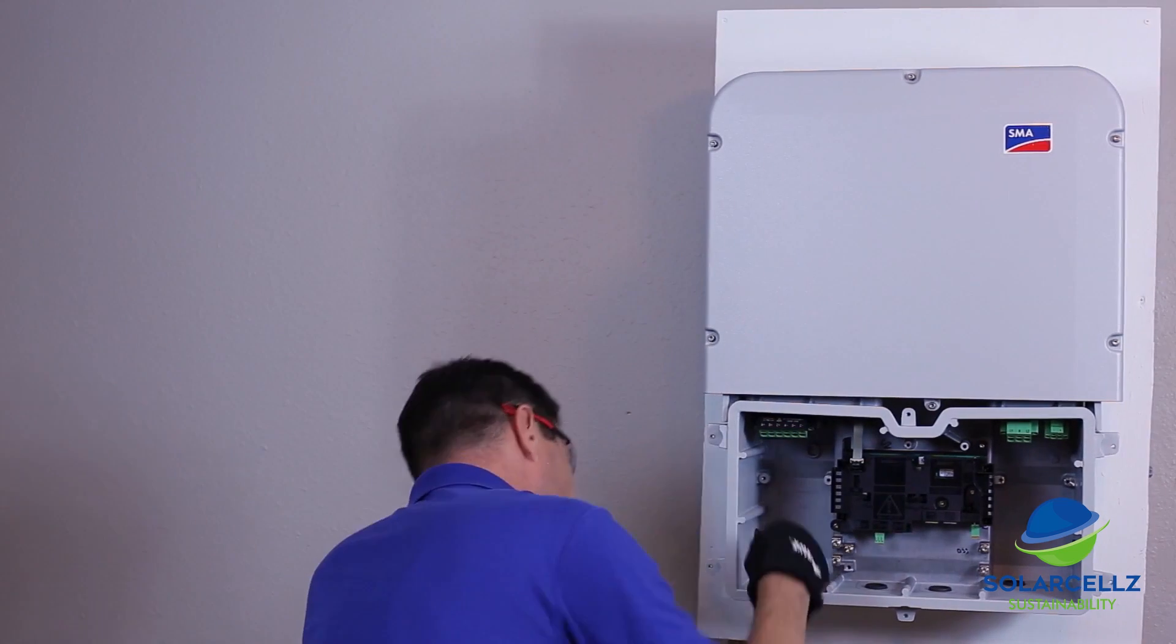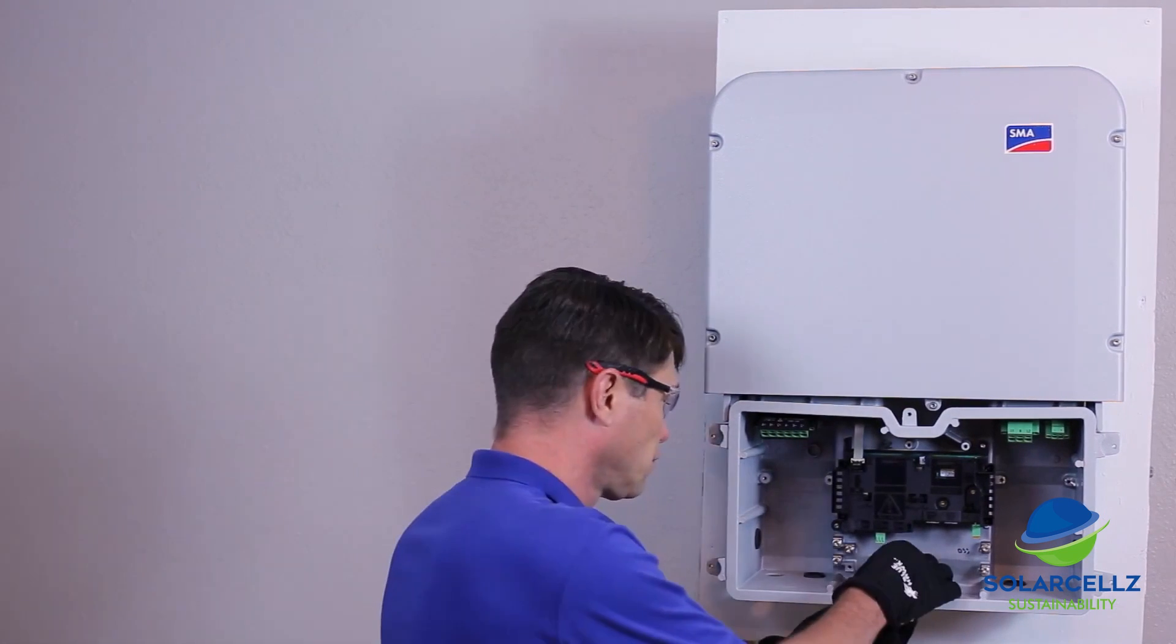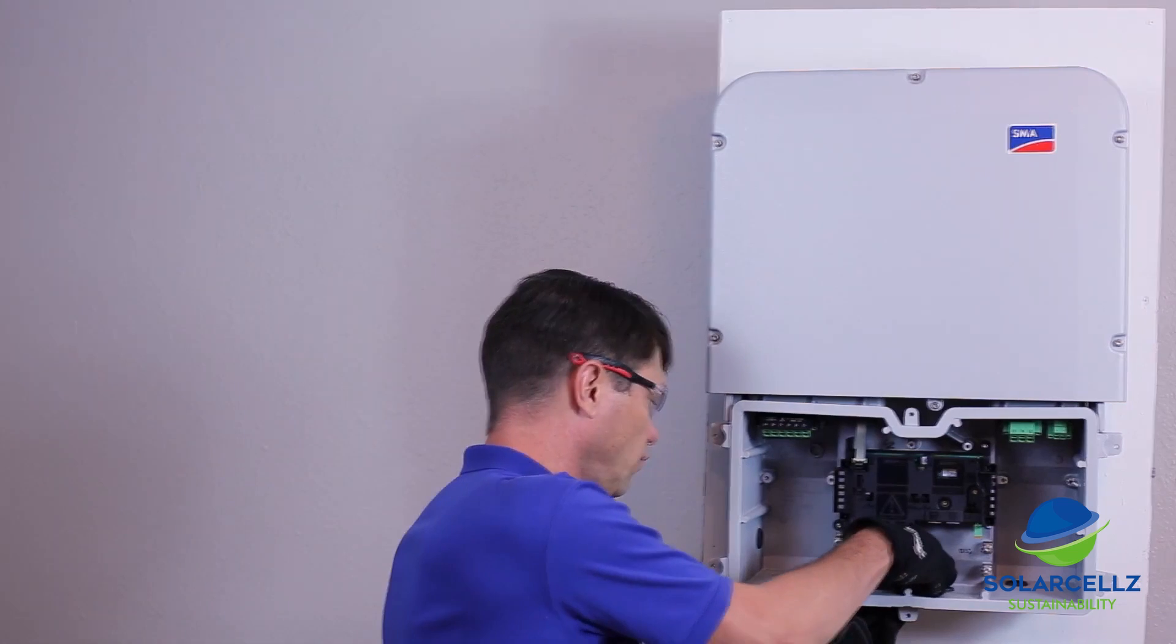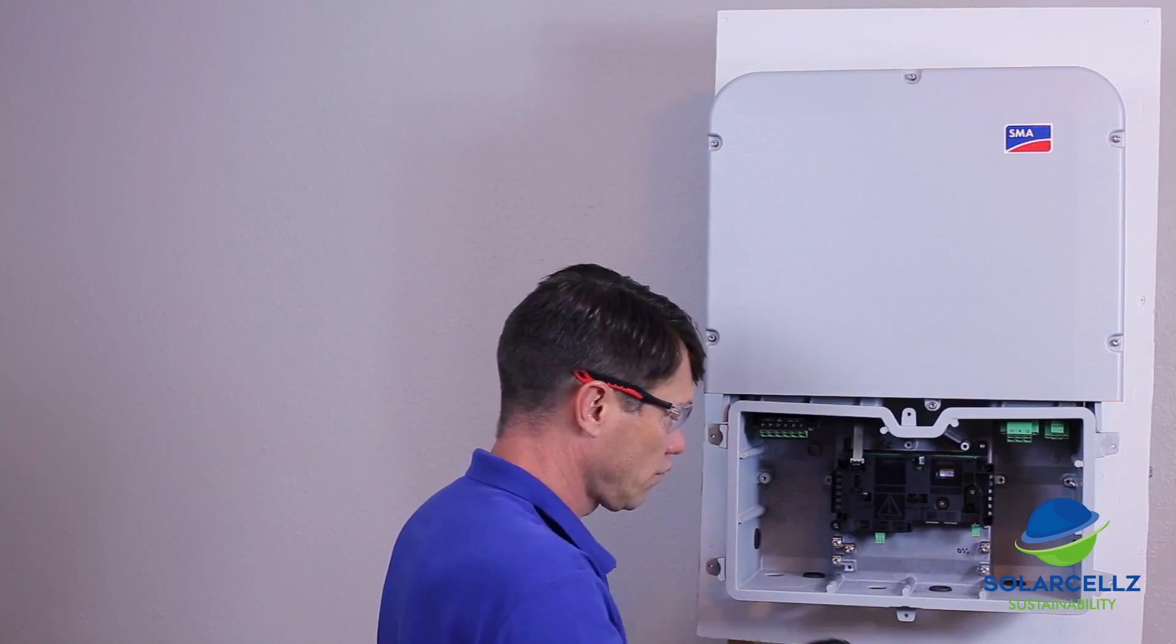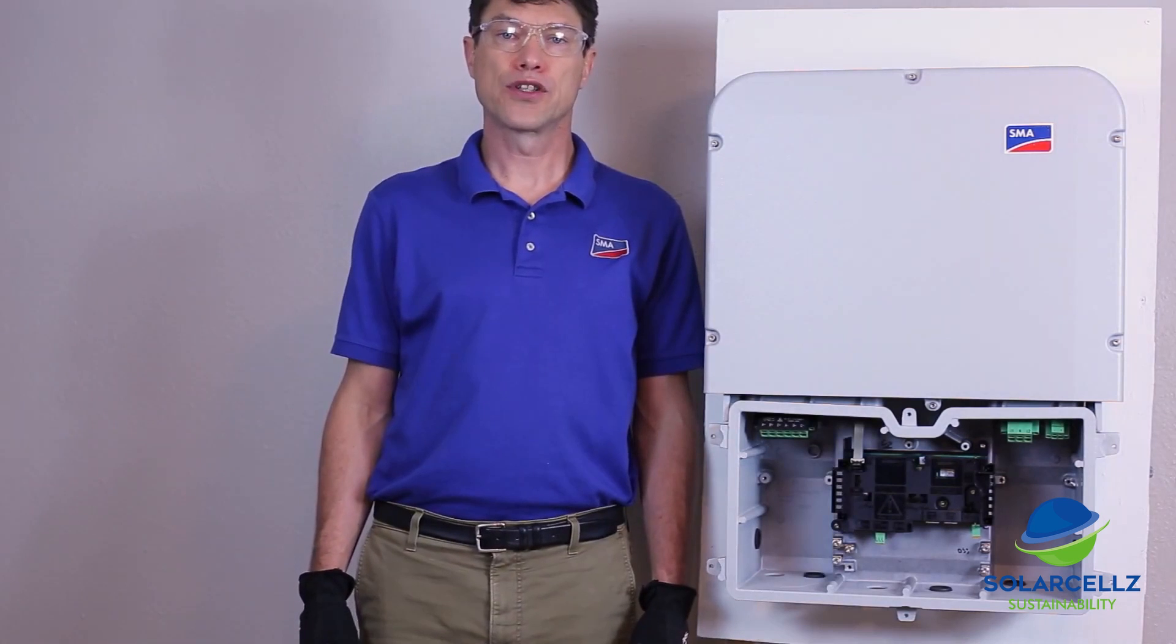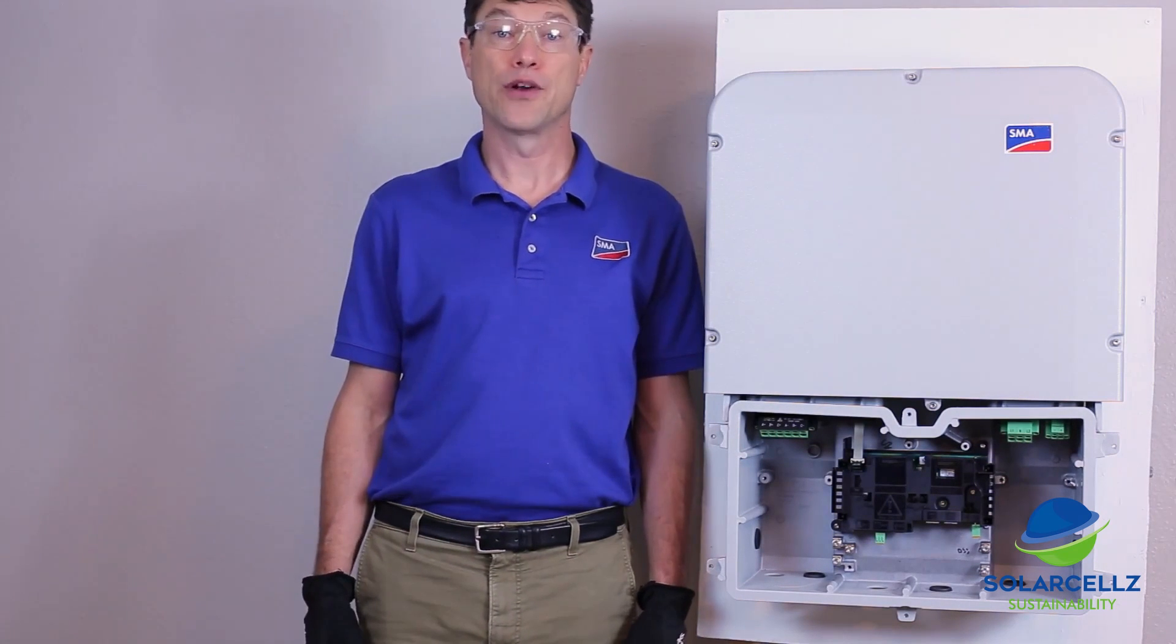Note that one AC and one DC knockout are taped shut; the remaining six three-quarter inch knockouts are plugged. Remove the tape or plugs from the knockout openings that will be used for conduit attachment, and ensure that all unused knockouts have plugs securely inserted.